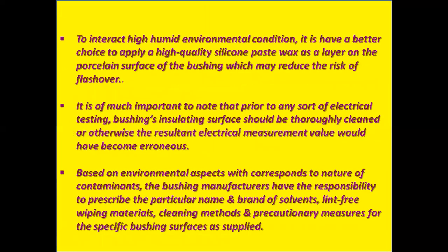To interact with high humid environmental conditions, it is a better choice to apply a high quality silicone paste wax as a layer on the porcelain surface of the bushing, which may reduce the risk of flashover. It is of much importance to note that prior to any sort of electrical testing, the bushing's insulating surface should be thoroughly cleaned, otherwise the resultant electrical measurement value would become erroneous.